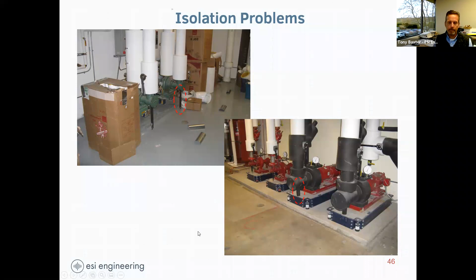One more here - very well isolated generator, but here we've got some conduit that comes into this box with unistrut going up and down. Well, geez, this generator is moving all over the place, and those forces are coming right here, right? This is a point of vibration, and if there's something sensitive nearby - you saw how that one medical air compressor caused vibration levels too high for that MRI - that's the potential here, right? That's going to cause noise and vibration from that generator someplace.